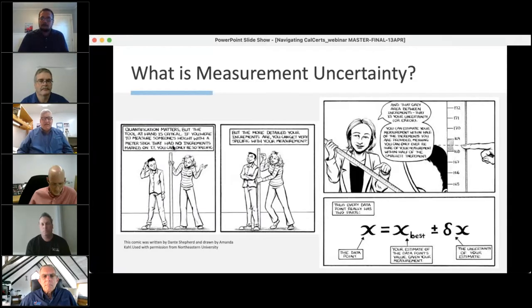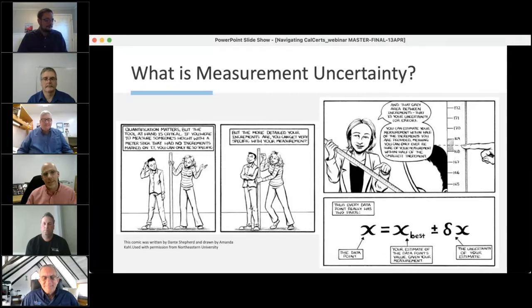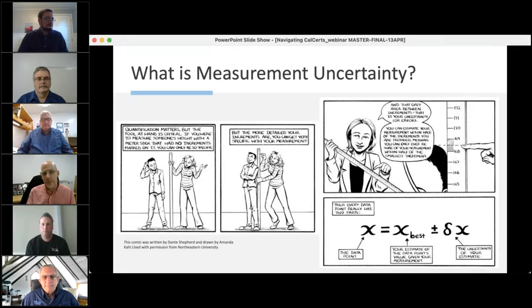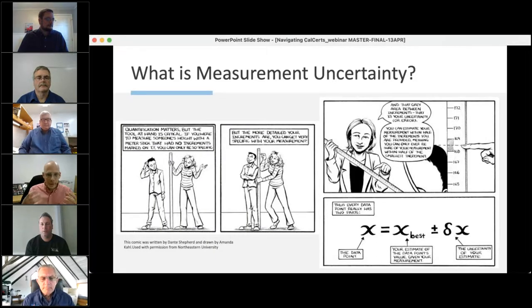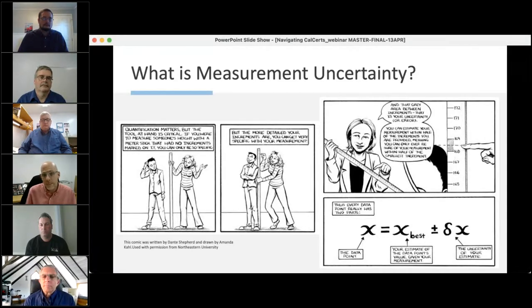Question: I'm calibrating in my lab, and my certificate comes back showing indeterminate. What should I do? You need to understand what your process tolerances are and what your process is capable of, so that you can take that indeterminate value and apply it to the readings collected during the calibration time frame. You need to run your reverse trace report, look at where measurements were taken, and how close those measurements were to the edge of the yellow or red zone on the pressure gauge shown earlier. You need to make a determination of whether that piece of equipment was on the edge of that indeterminate range and whether it impacted your process.